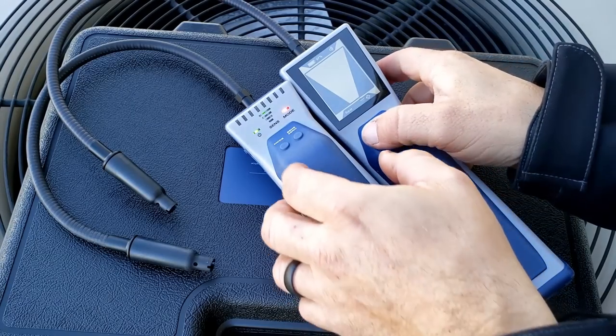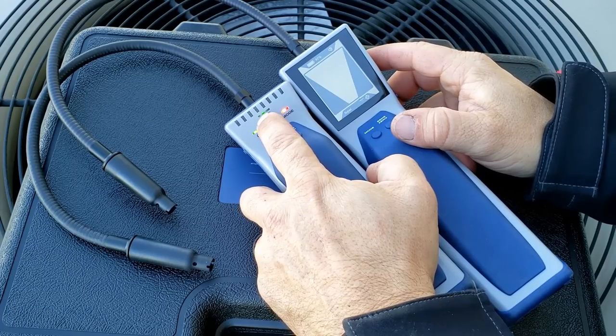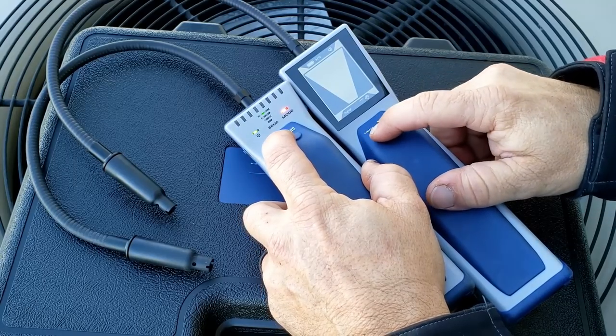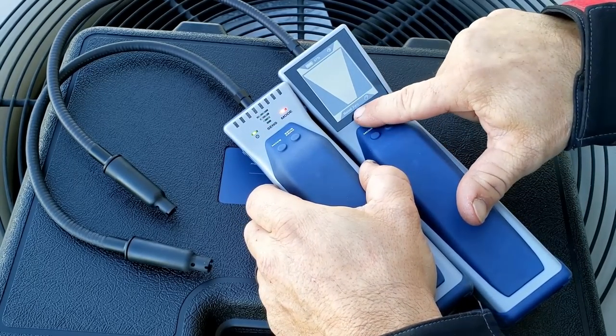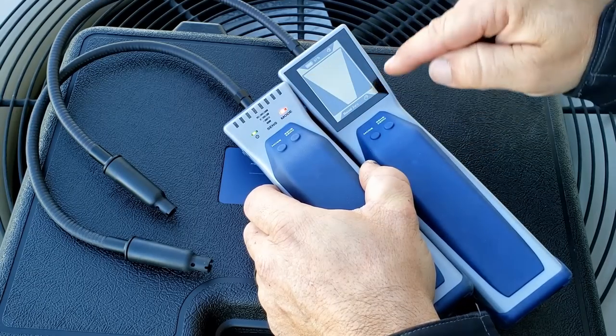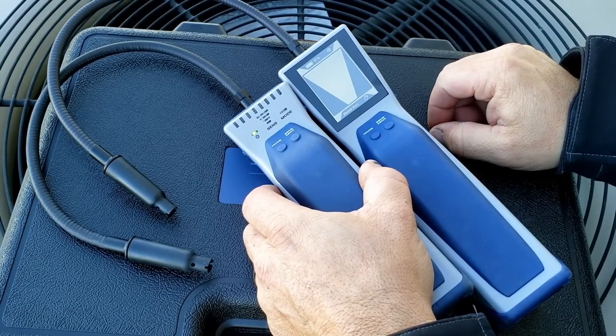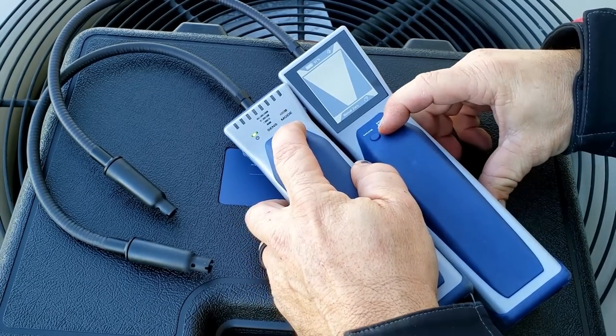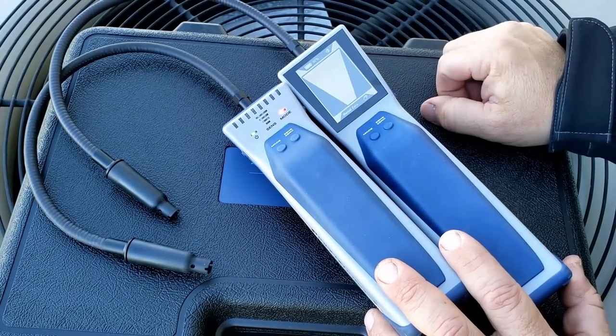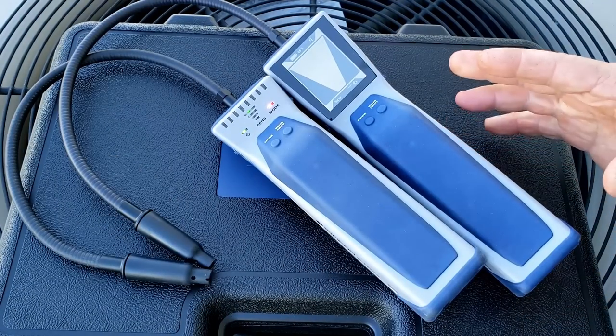Let's talk about the different modes. They're both currently in super mode — you can see it's all the way at the highest and it says it right here. If you hit the mode button, it jumps to manual zero, signified by the blinking light on the D-Tec 3, and the Stratus shows 'manual zero' at the bottom of the screen. To actually zero out, you just hit the zero button. The D-Tec 3 will do a flutter to confirm, and the Stratus will display 'zeroing' at the bottom of the screen.